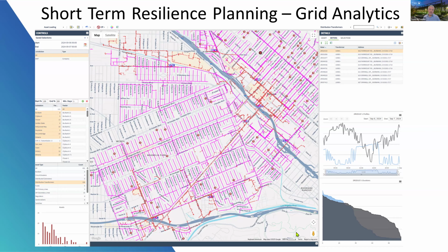So to give you an example, over this last summer, before the summer occurred, we replaced all of our transformers above 170%, and for the ones between 150 and 170%, we provided pre-engineered solutions. That's more for the resilience planning piece, so that if something happened to one of those transformers, our crews would know what they needed to do as far as what size that transformer needed to be, or how they needed to shift load on that particular transformer. Next slide, please.